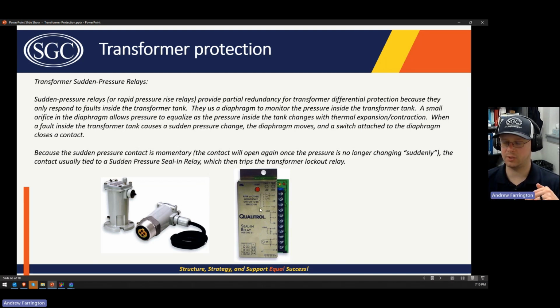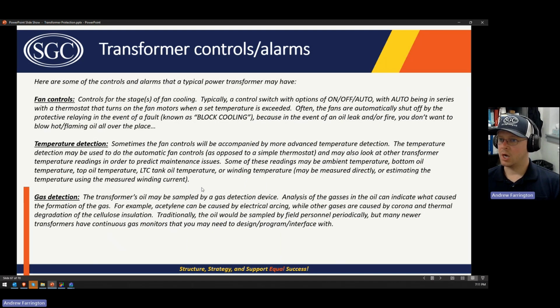So you'd have a seal-in relay. This is an example of that. The sudden pressure relay trips the seal-in relay, and that has contacts that are maintained long enough to trip the lockout relay for the transformer. There are also fan controls. Those are looking at the ambient temperature and the temperature of the oil, potentially the ambient temperature, but almost certainly the temperature of the oil or the hotspot winding temperature. And then that'll allow you to control the fans either manually or automatically based on a thermostat contact.